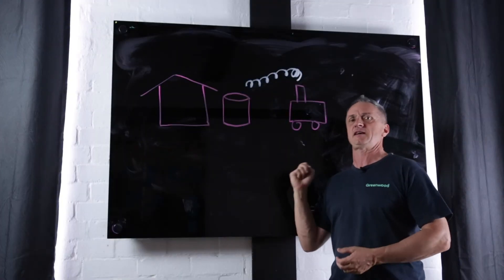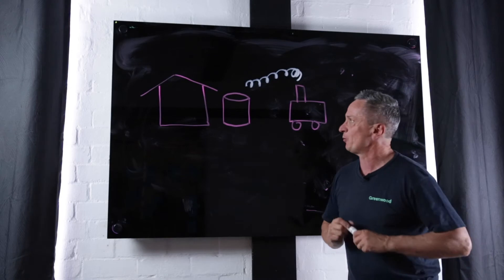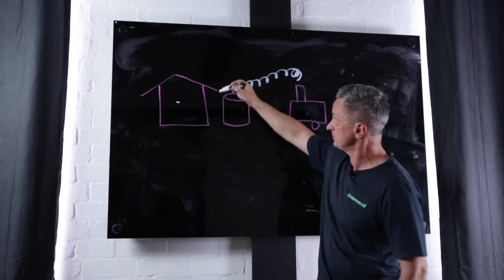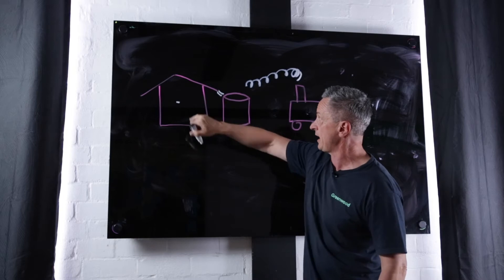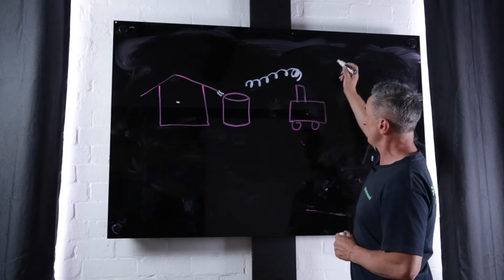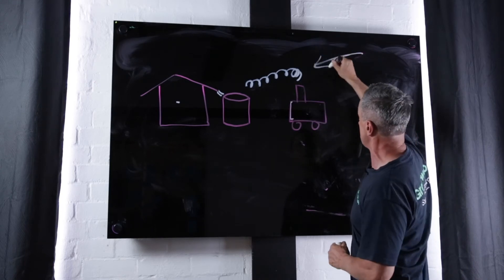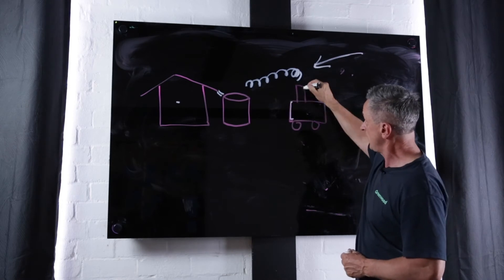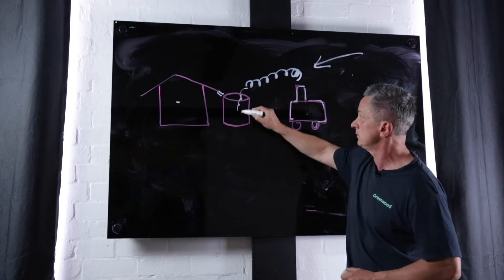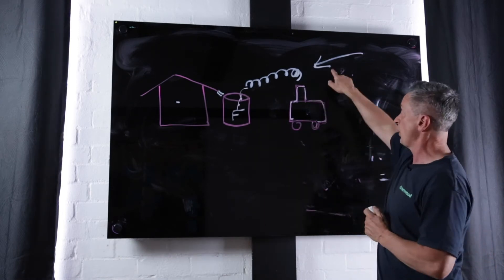In this picture you can see — best I can do — we have a house, it's completely off-grid. We have a water tank which is fed by the guttering on the house. And where do we put the generator? Be very aware of the prevailing winds in the area in which you're going to install this generator. If you put the generator upwind of the prevailing wind, there's a high chance that particulate matter — especially diesel particulate matter, which is really horrible stuff — will foul the water supply. It's a big thing, so be aware of prevailing winds.